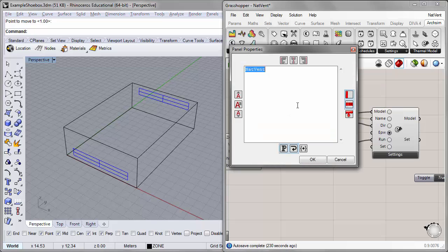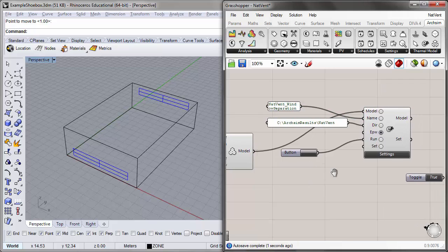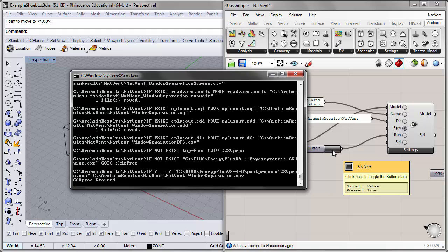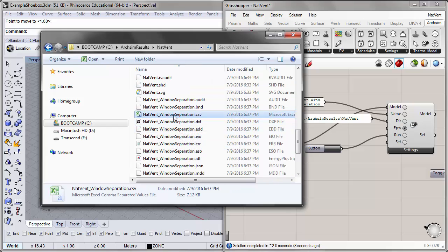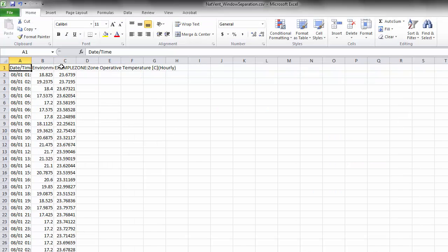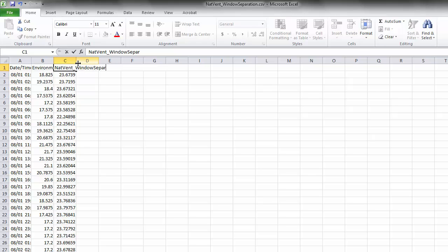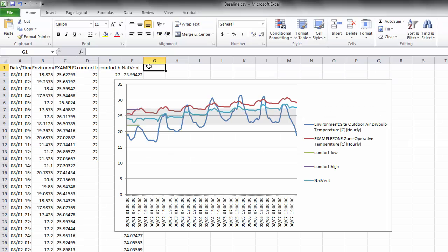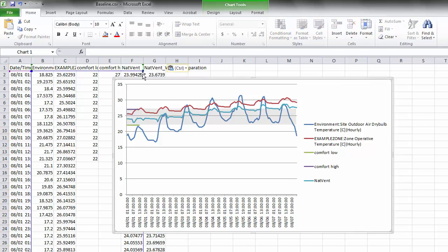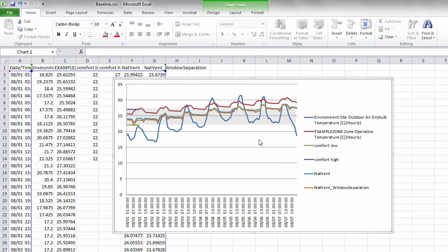I'll give this variant a different name: NatVent Window Separation. I'll run the same simulation and go back to our results location. I'll open the CSV file just created, copy the operative temperature for this variant — renamed NatVent Window Separation — and paste it into our first Excel file for comparison against the baseline. I'll expand the chart data set. You can see there was a slight decrease in the operative temperature profile as a result of the change in window configuration — it's a subtle but slight improvement.